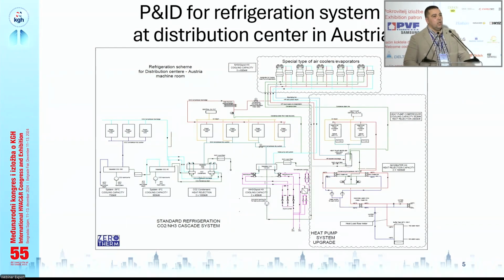CO2 condensers, which are, in our opinion, the first crucial point of the system, because these two CO2 condensers are also working as ammonia evaporators. These units have to be very well manufactured with high-end materials, because in our opinion, if leakage or damage occurs on these heat exchangers, it can create a major breakdown of the system. The rest of the system from the ammonia side is pretty much a standard refrigeration system. We have a dry suction going to piston compressors for the ammonia, and a hot gas discharge going to the nowadays standard design, which goes through the heat exchanger for a recovery system. And after that, we have a motor valve that goes to the next crucial point of this system.